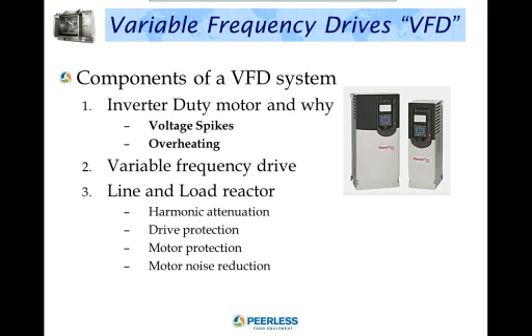The installation of load reactors with drives and motors can reduce the high frequency currents in the motor and protect the motor from long lead effects. Basically, the reactor attempts to recreate a sine wave, thus improving overall system performance, reliability, and efficiency. It may reduce audible noise by as much as 5 dB. Tests have shown motor temperatures can drop by as much as 20 degrees Celsius when using a harmonic compensated 5% impedance load reactor.